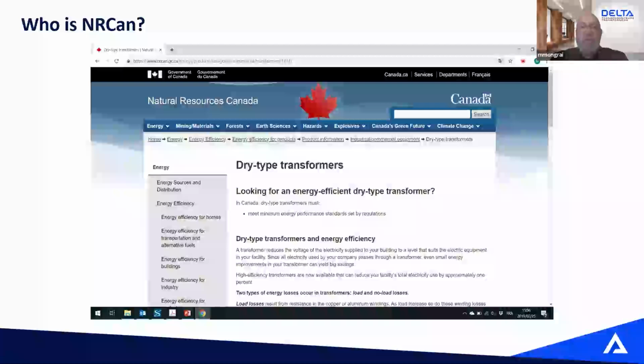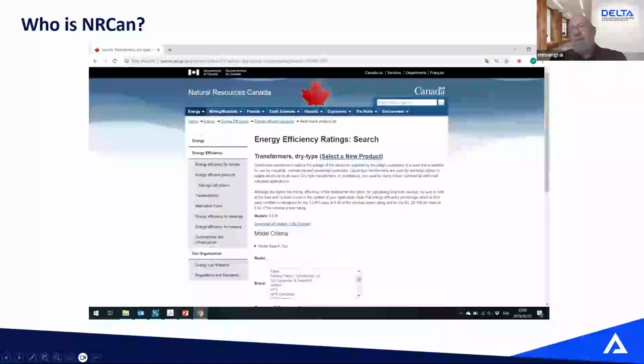So NRCan is government, so they have a nice website. And when you dig a little bit on that website, you can find the pages about dry type transformers. And on that website, you have the data of all manufacturers. So when we build a transformer that complies with NRCan, we have to provide them with the data, and then they will update their website with that data. So if you go there and you look for any manufacturer, Delta, Hammond, Marcus, whoever, Rex, the data will be there. It's the government, so they're not very efficient. So sometimes when we send them the information, it can take up to 18, 24 months for them to update the website. So if you don't find the information, it's not because it's not there. It's because our governments are not very efficient sometimes, like the transformers.